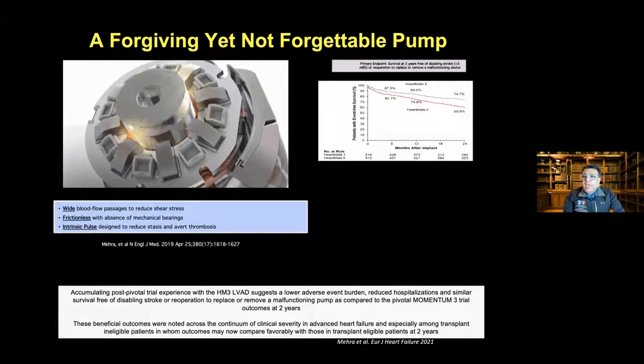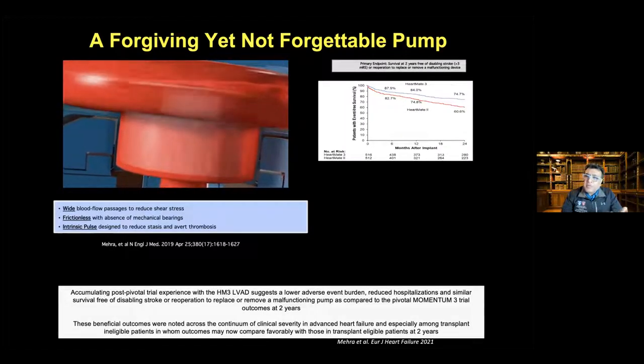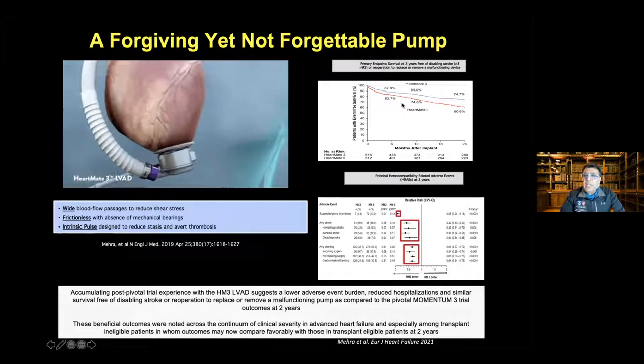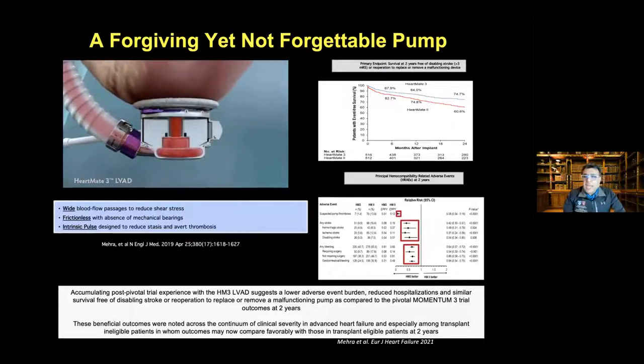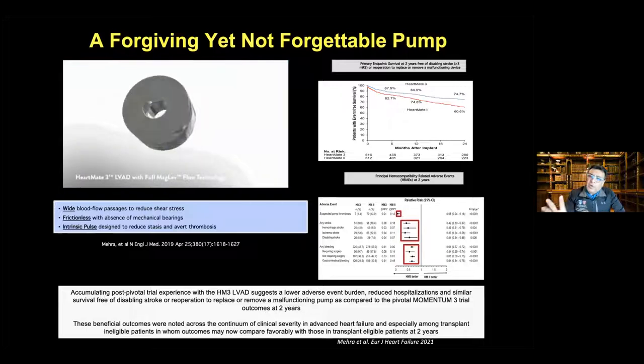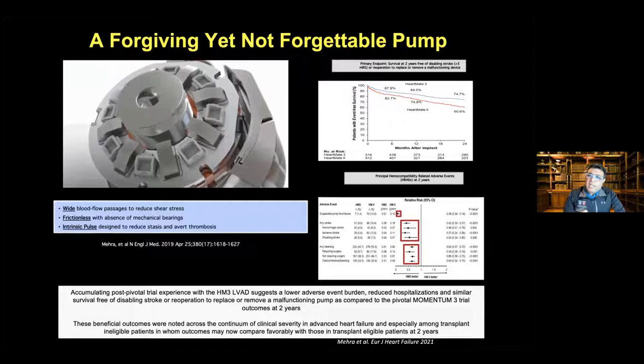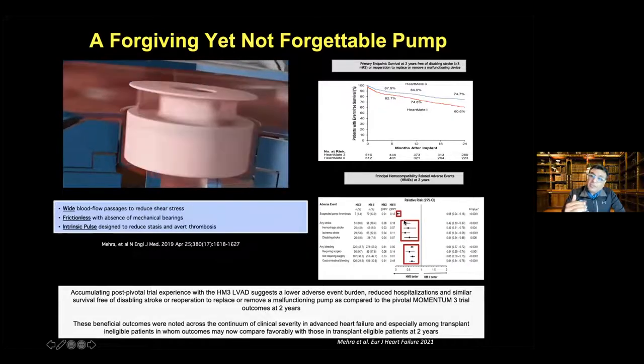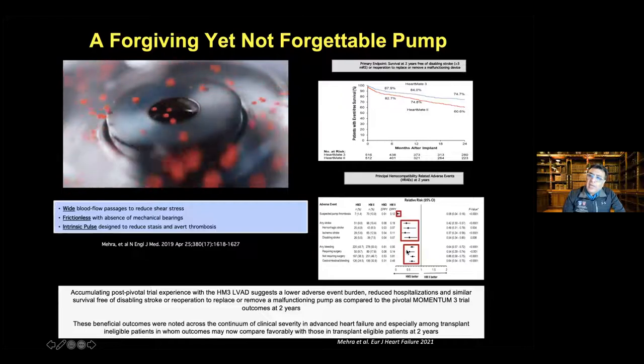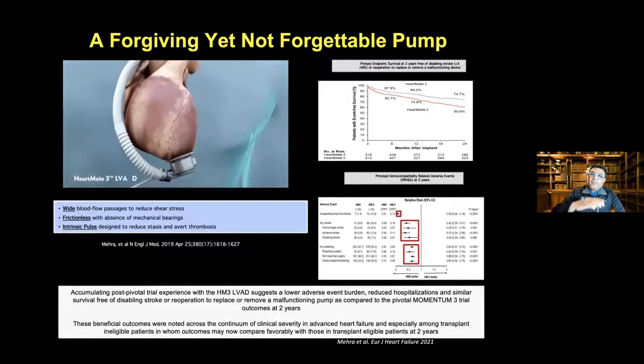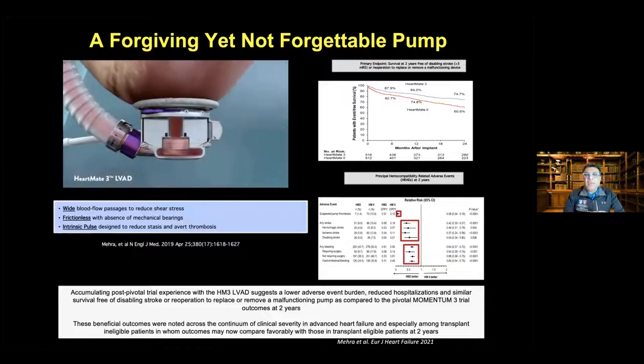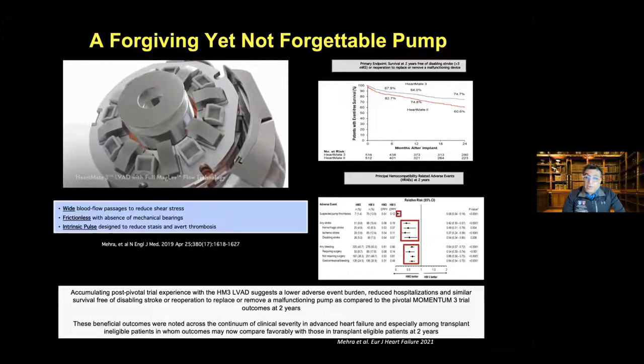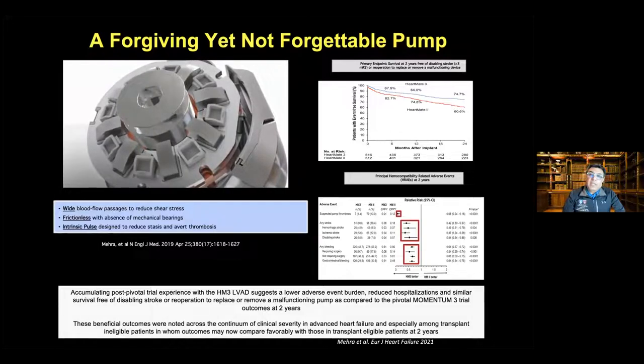The pulse algorithm is created by moving the rotor speed up and down at a fixed asynchronous pulse rate of about 30 beats per minute, designed to reduce stasis and avert thrombosis. The initial trial was the Momentum 3 trial — the largest trial in the LVAD field, which I had the privilege of chairing. The final outcome suggested clear superiority of this device with marked decrease in hemocompatibility-related complications: near elimination of pump thrombosis, halving of stroke rates, and a third reduction in bleeding events.